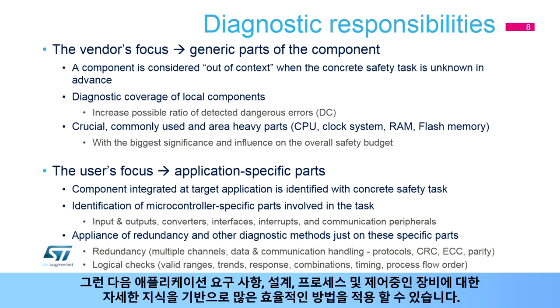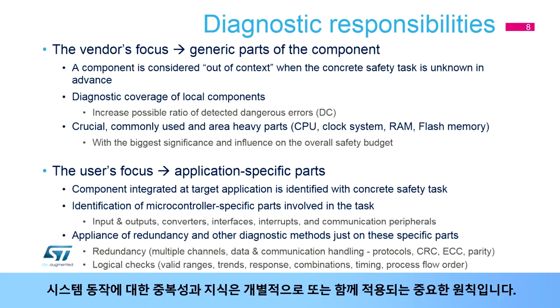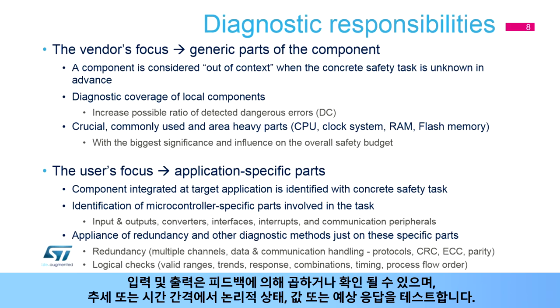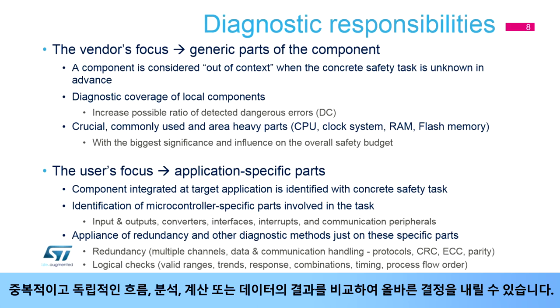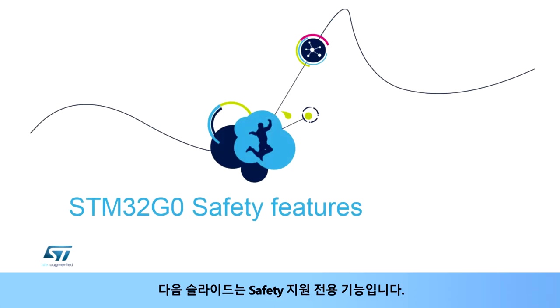Once a microcontroller is included in an application design and the safety task is specified, the safety support can be deployed much more efficiently and cover just the very specific parts of the microcontroller involved in the required safety case. Many efficient methods can then be applied based on detailed knowledge of the application requirements, its design, the process, and the equipment under control. Redundancy and knowledge of the system behavior are crucial principles applied either separately or together. Inputs and outputs can be multiplied or checked by feedback, tested for logical state, value, or expected response in trends or time intervals. The processes can be monitored for correct timing and flow order, and correct decisions can be made based on the comparison of results from redundant and independent flows, analysis, calculations, or data.